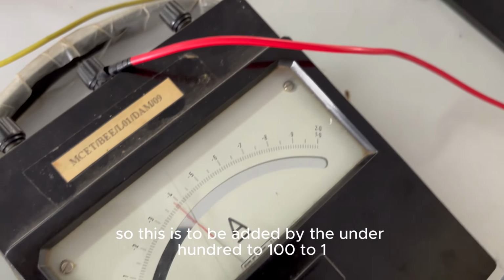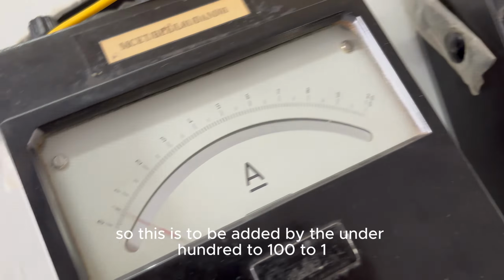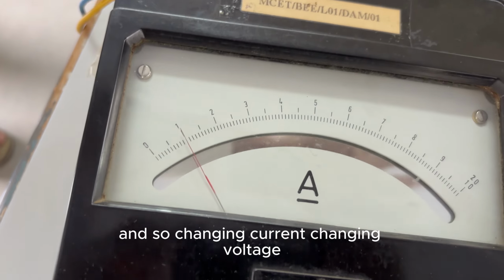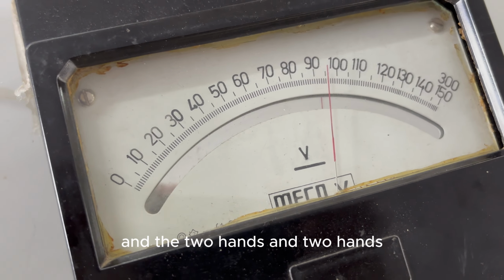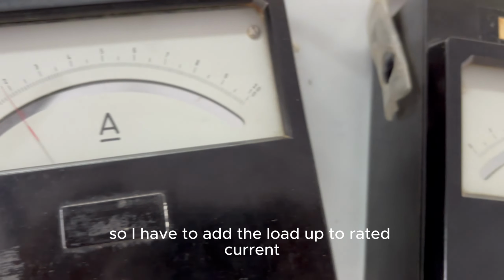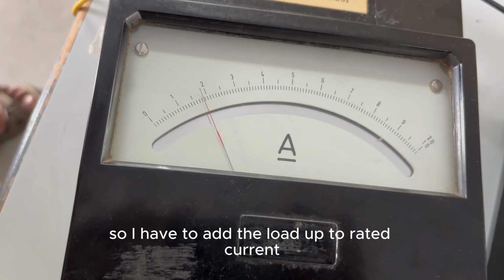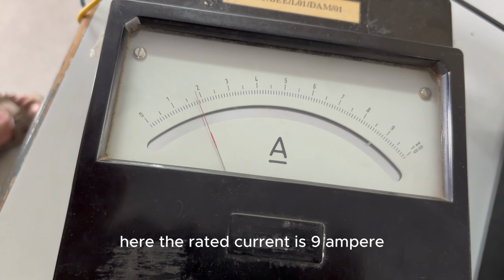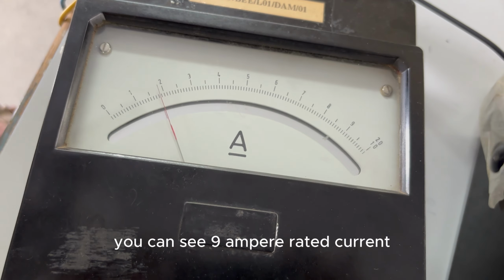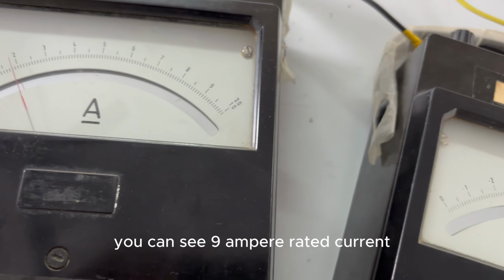Then add another 2 amps, another 2 amps, noting the change in current and voltage, and so on. I have to add the load up to rated current. Here the rated current is 9 ampere as per the nameplate.